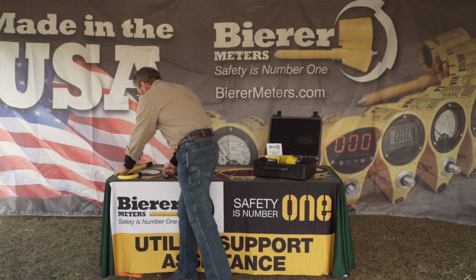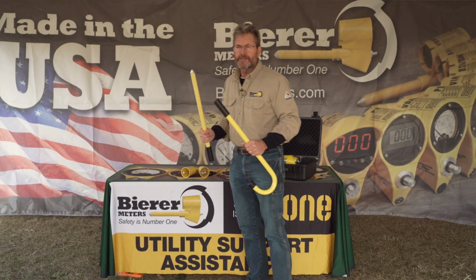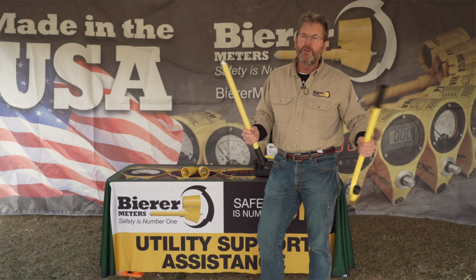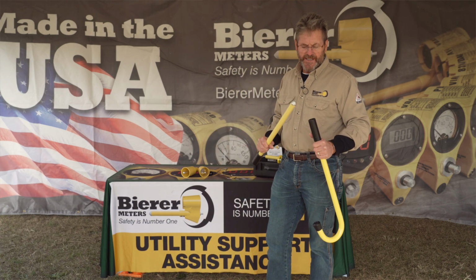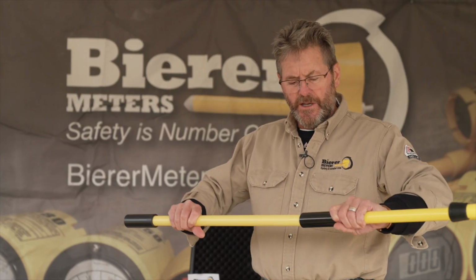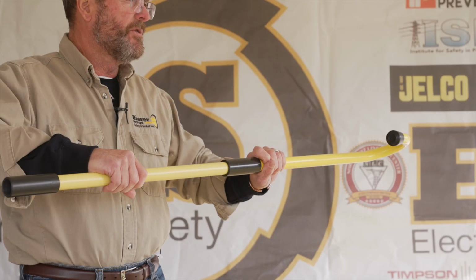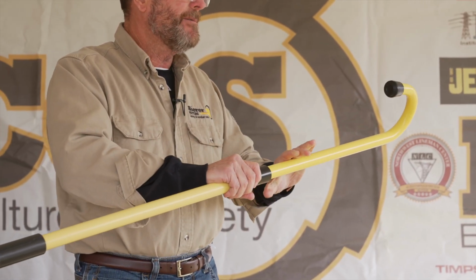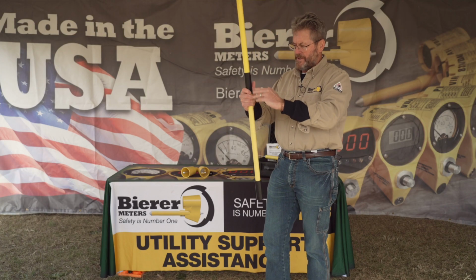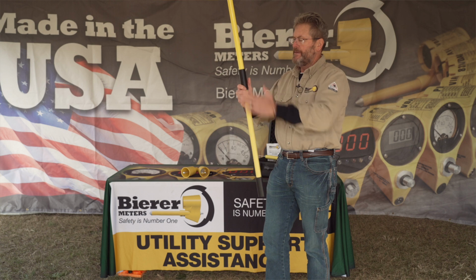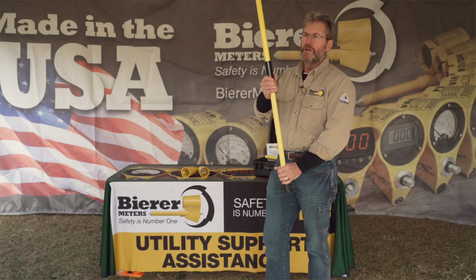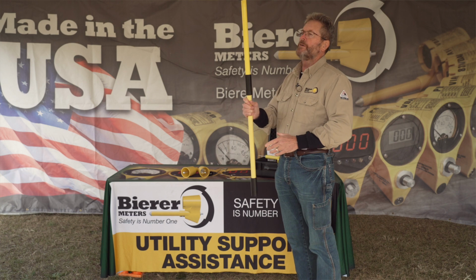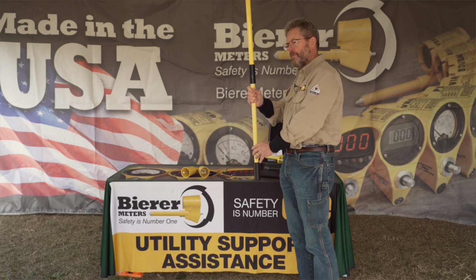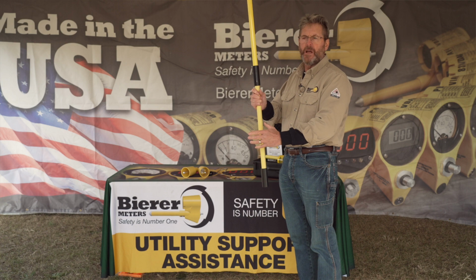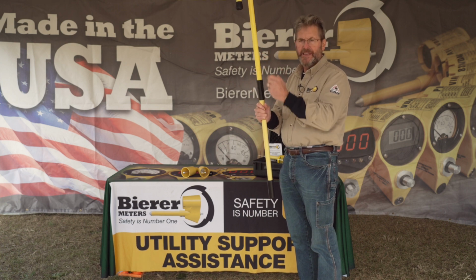Also, keep in mind if you're working transmission and you're using, say, the wireless PD800W, the wireless phasing voltmeter, then you're going to use a shepherd's hook. You simply take the shepherd's hook, you screw both of these together, and this goes from 2 foot to a 4 foot accessory shepherd's hook. What will happen is this will allow your PD800W to come into the corona of that transmission line, and it'll still pick up that phase angle.